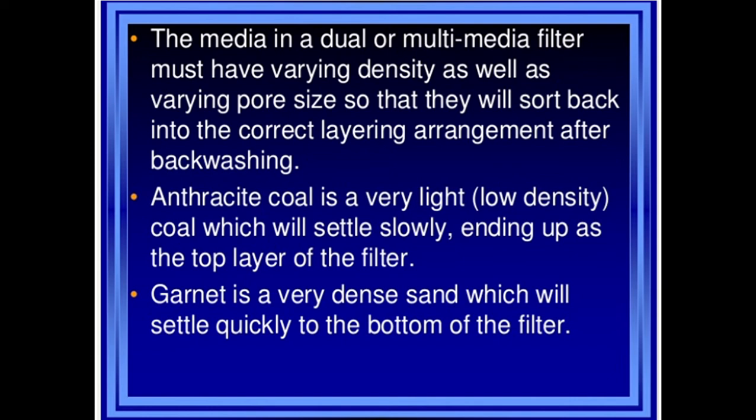Anthracite coal is very light, having low density, which will settle slowly, ending up as the top layer of the filter. Garnet is a very dense sand which will settle quickly to the bottom of the filter.